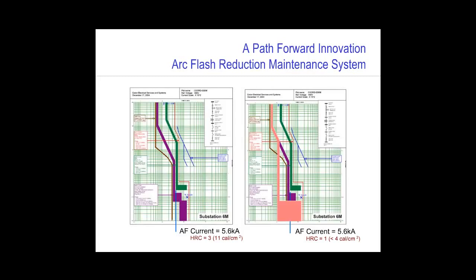That would result in a hazard risk category of 3 or 11 calories per centimeter squared. So if I actually had someone working downstream of this substation, I could set this trip unit into a maintenance mode using the ARMS capability. What happens then is that the feeder breaker curve shifts over to the left, as shown on the right in the pink colored curve. And in this case you can see moving that curve over with the same arcing current would reduce the hazard risk category down to 1 or less than 4 calories per centimeter squared.